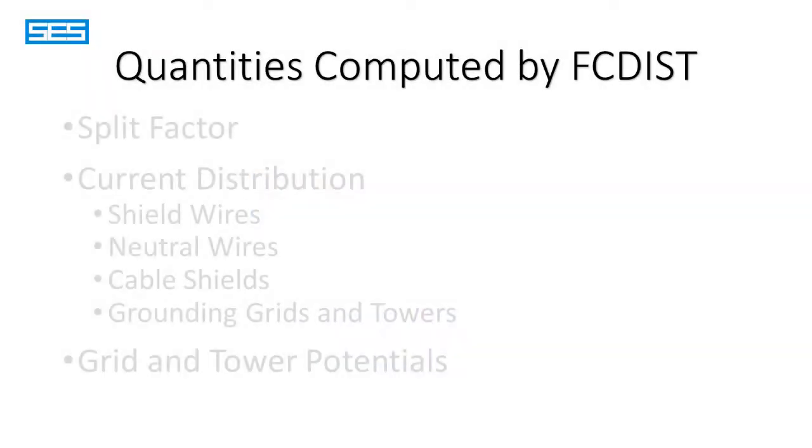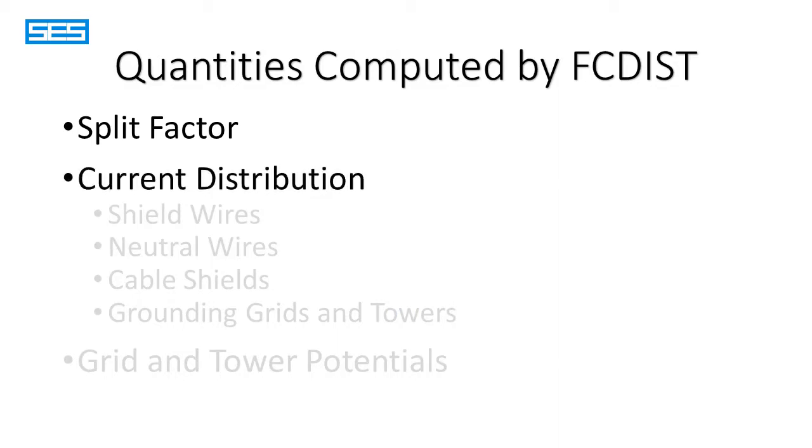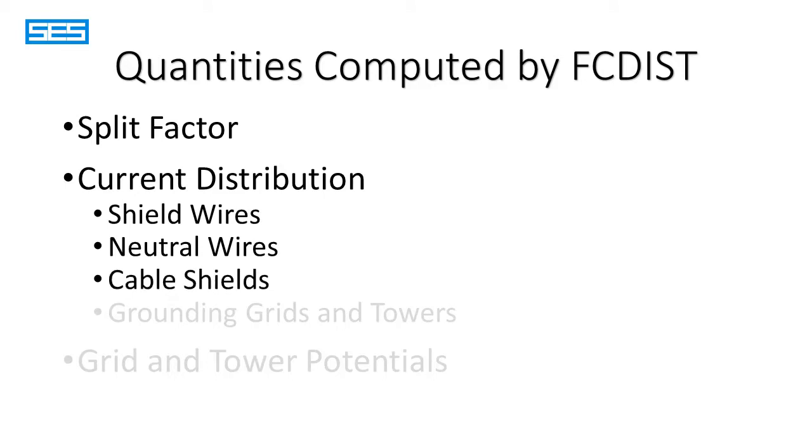Important quantities that can be calculated by FCDIST include the current division factor or split factor, which is described in the IEEE standard, the current distribution along shield wires, neutral wires, cable shields, and similar metallic paths, as well as grounding grids and towers.